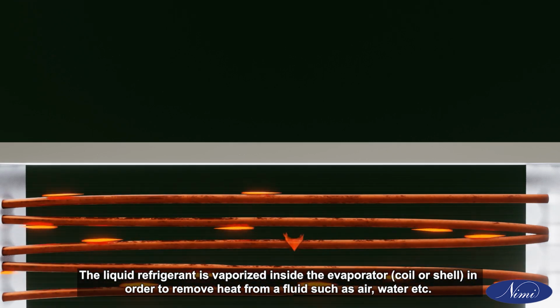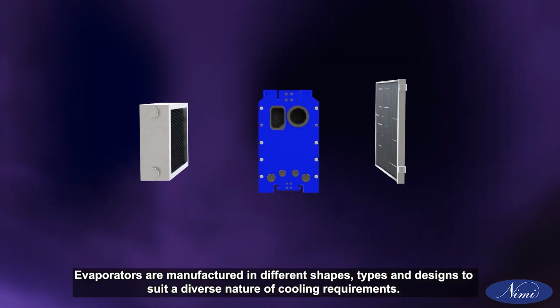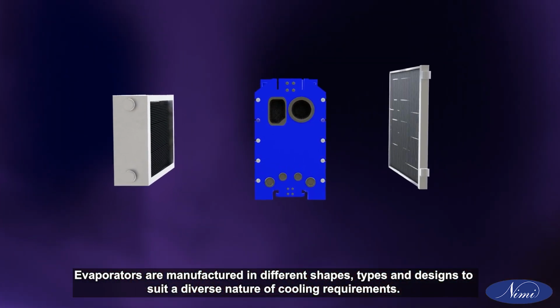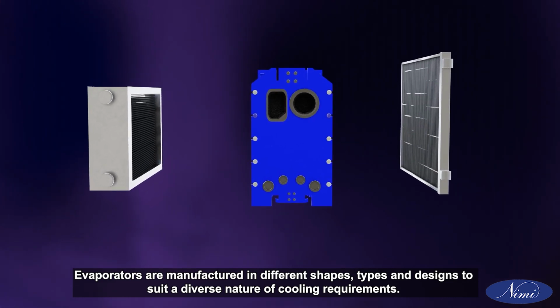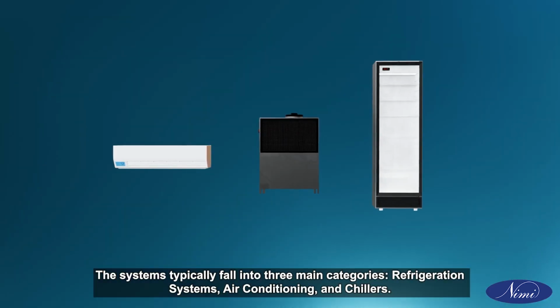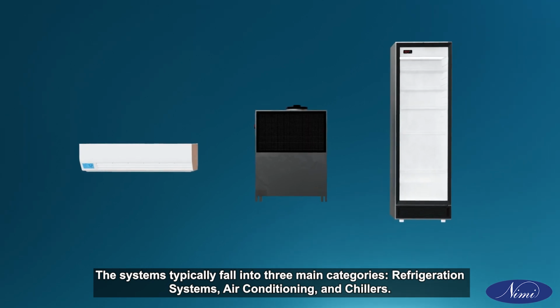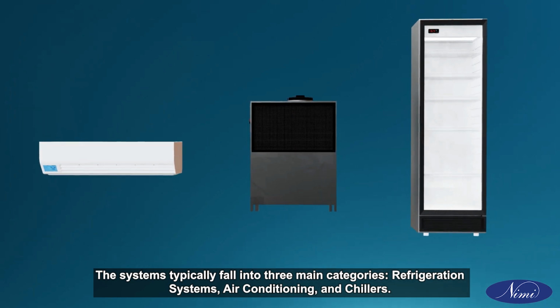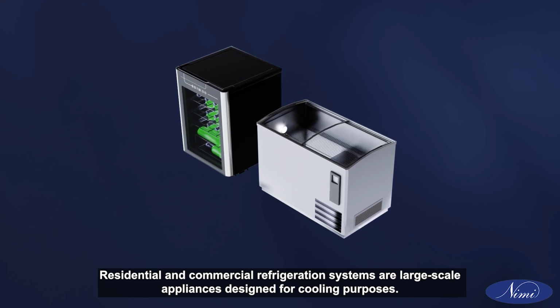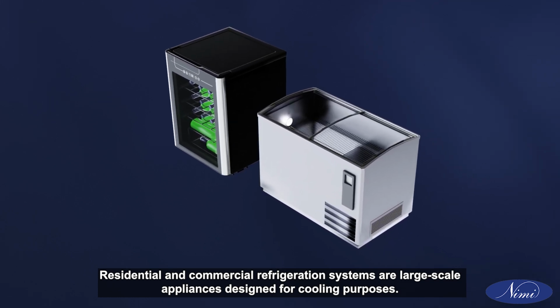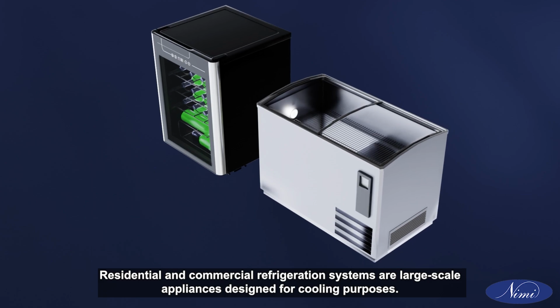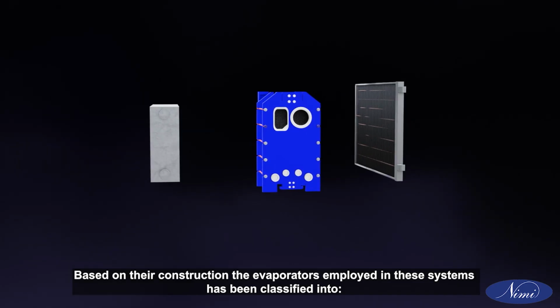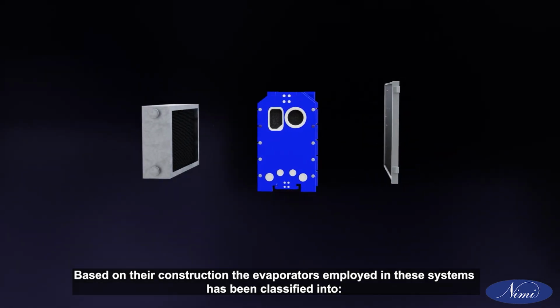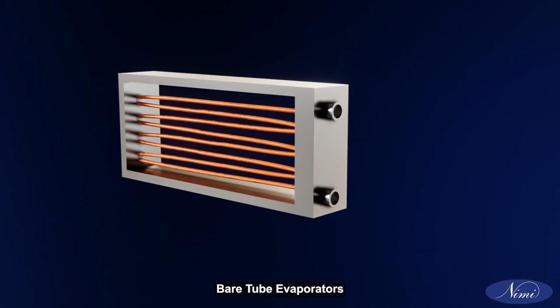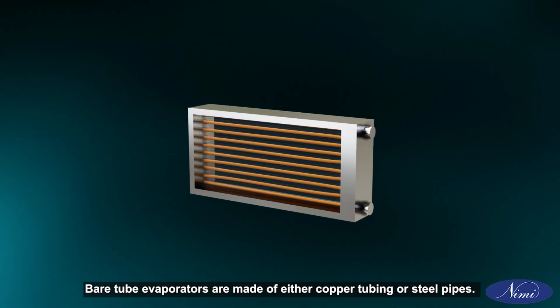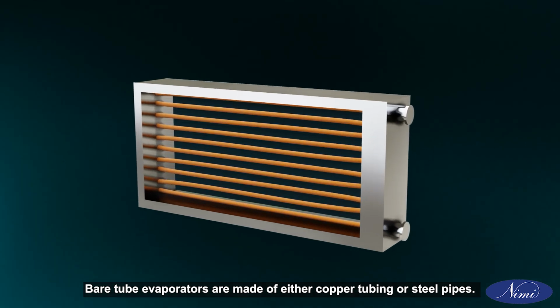The liquid refrigerant is vaporized inside the evaporator coil or shell in order to remove heat from a fluid such as air, water, etc. Evaporators are manufactured in different shapes, types and designs to suit a diverse nature of cooling requirements. The systems typically fall into 3 main categories: refrigeration systems, air conditioning, and chillers. Residential and commercial refrigeration systems are large-scale appliances designed for cooling purposes. Based on their construction, the evaporators employed in these systems have been classified into bare tube evaporators. Bare tube evaporators are made of either copper tubing or steel pipes.